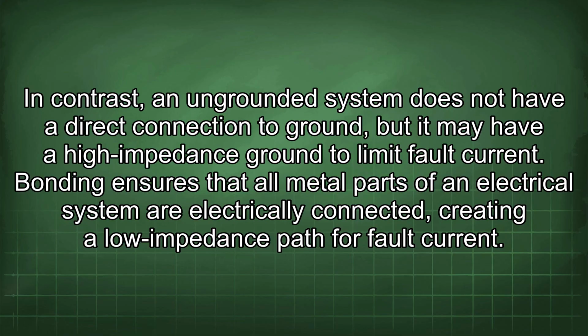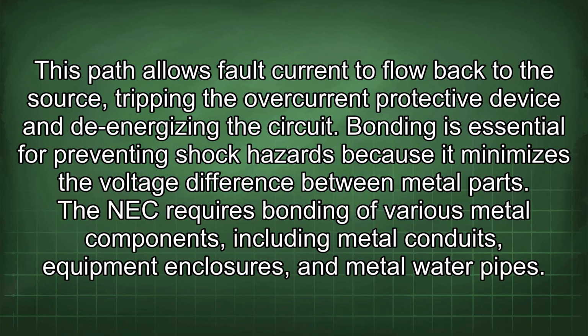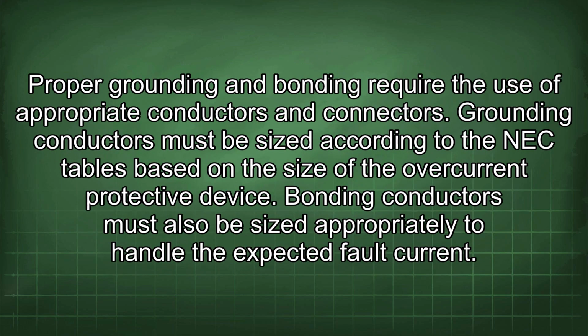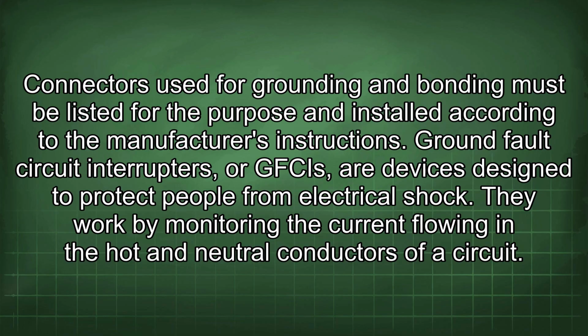Bonding ensures that all metal parts of an electrical system are electrically connected, creating a low impedance path for fault current. This path allows fault current to flow back to the source, tripping the overcurrent protective device and de-energizing the circuit. Bonding is essential for preventing shock hazards because it minimizes the voltage difference between metal parts. The NEC requires bonding of various metal components, including metal conduits, equipment enclosures, and metal water pipes. Proper grounding and bonding require the use of appropriate conductors and connectors. Grounding conductors must be sized according to the NEC tables based on the size of the overcurrent protective device. Bonding conductors must also be sized appropriately to handle the expected fault current. Connectors used for grounding and bonding must be listed for the purpose and installed according to the manufacturer's instructions.